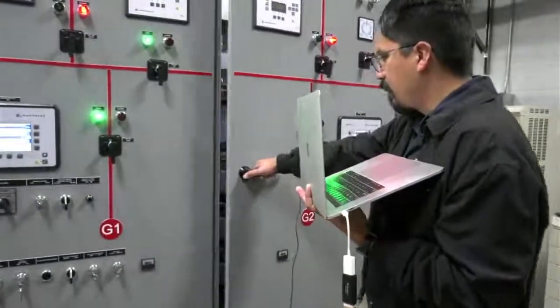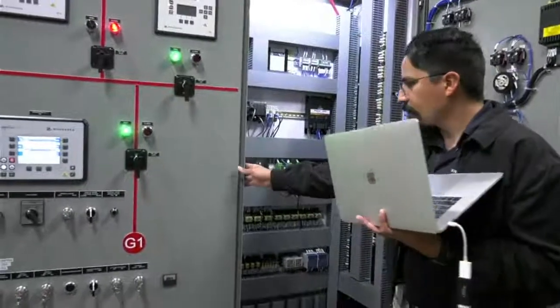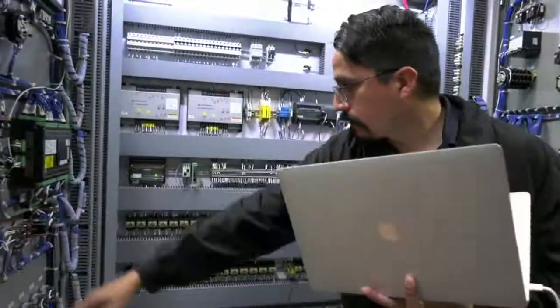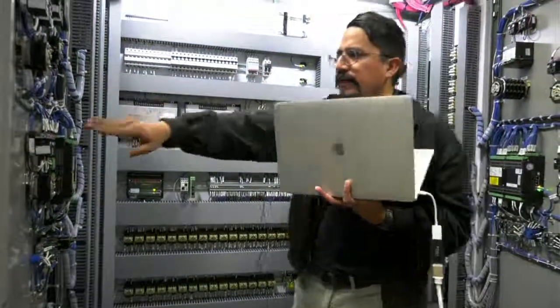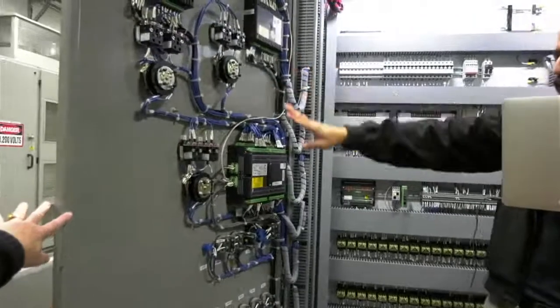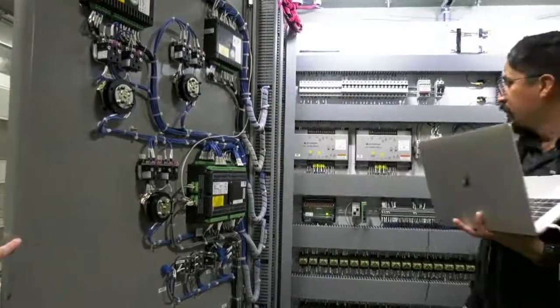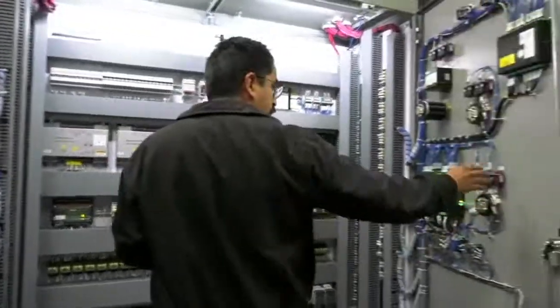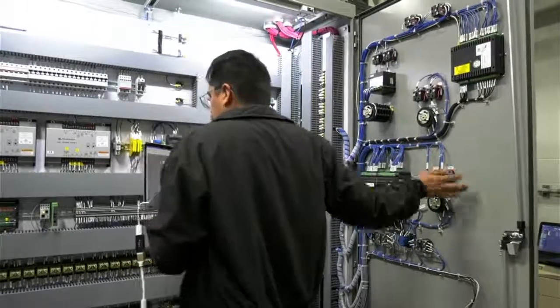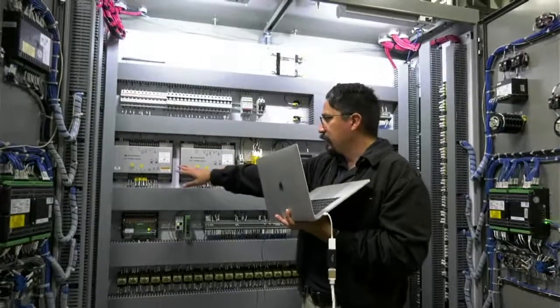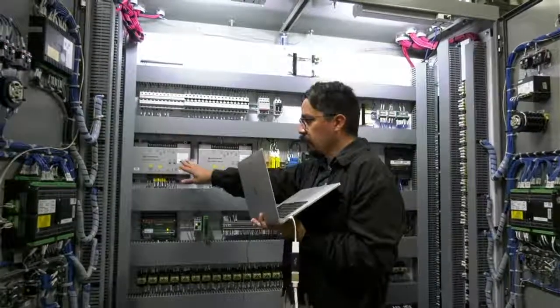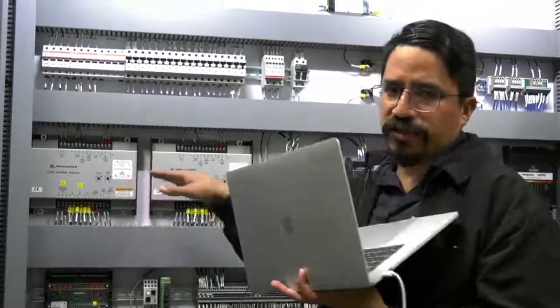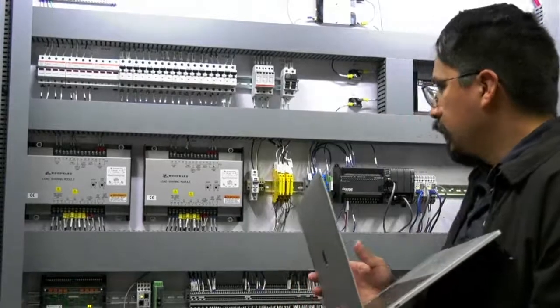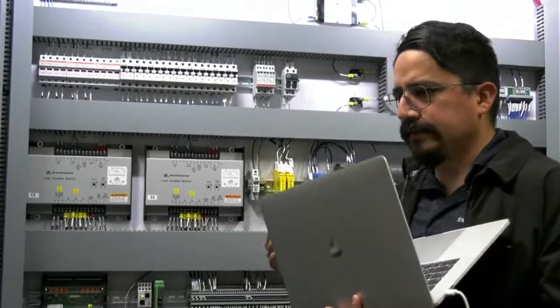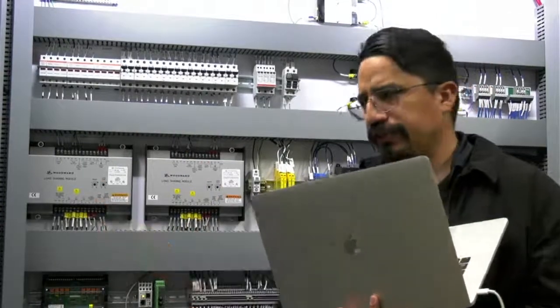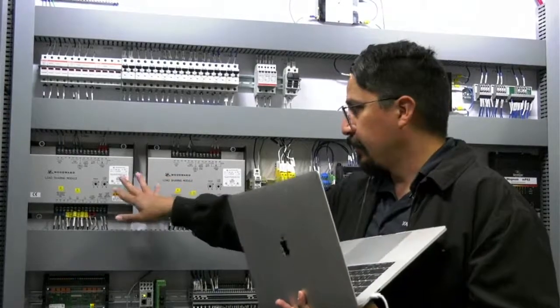Inside of the cabinet, right here we have the main components on the door. As we said, this is the wiring for each component. We have two doors. They are like mirrors, so they have the same components wired. On the back, we can see those load sharing modules. Those are Woodward, and they are in charge of the manual control. They help the manual mode in a way that the EasyGen can be outside of the picture, and the load sharing is done by these components.